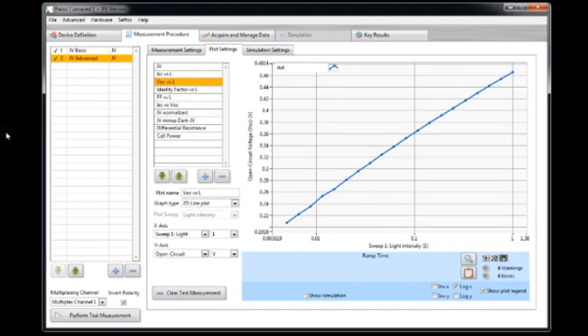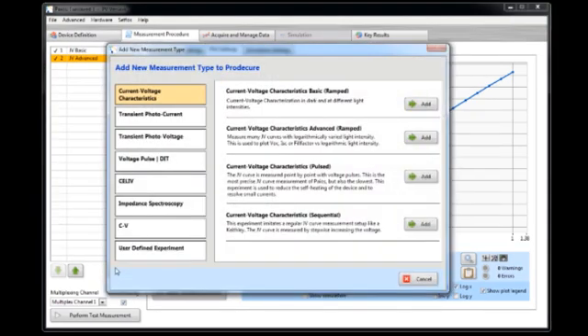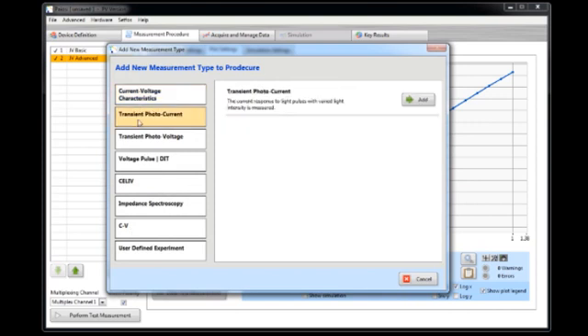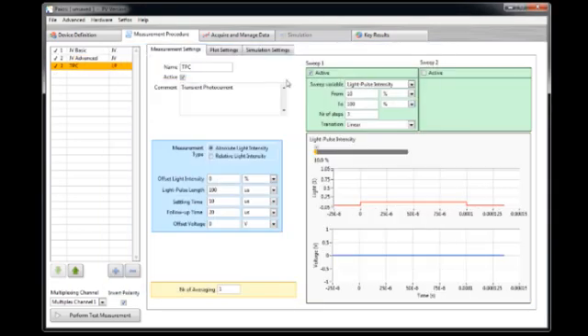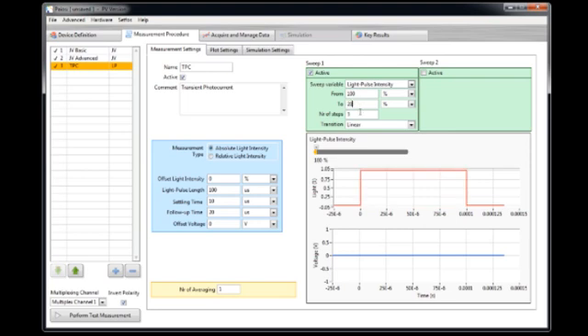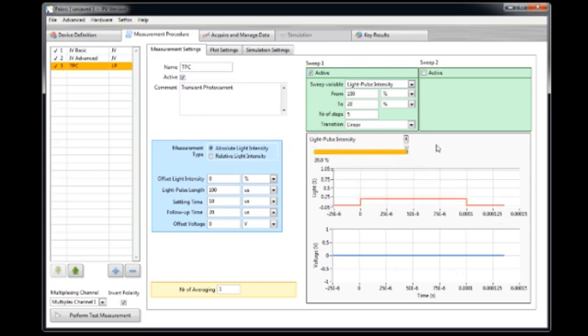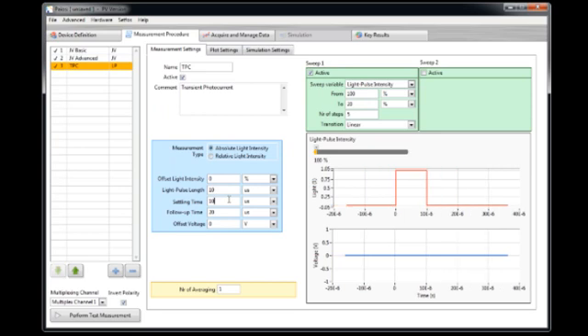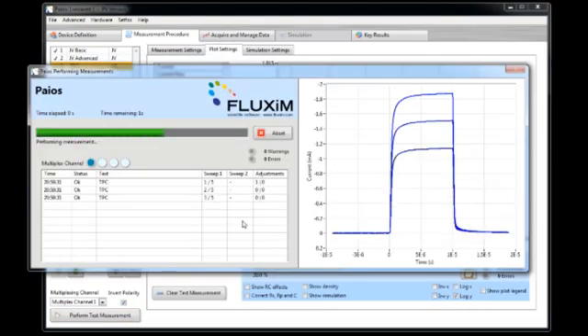Let's now continue with transient measurements. Here we added a JV curve before. Now I would like to add a transient photocurrent. Here the cell is flashed with a light pulse. And on this graph here you see a preview. So you see the light pulse. And what I do now is I vary the light intensity. But I want to make a light pulse quite short. So I make it 10 microseconds and 5 microseconds waiting time before and afterwards.